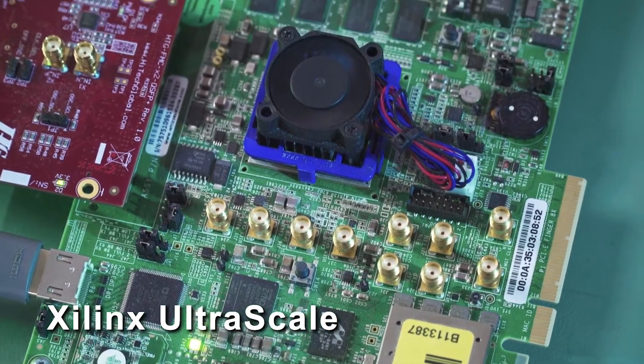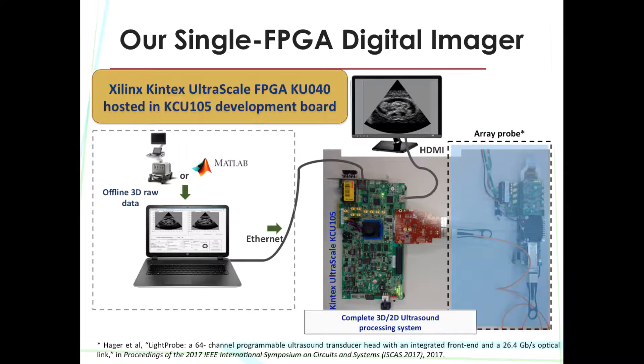The central part is the board realizing our end-to-end processing system, while supporting two means of data input: real-time by optical connection with a probe for the 2D imaging case, and simulated input by Ethernet connected to a laptop for 2D and 3D, in addition to providing HDMI video output.